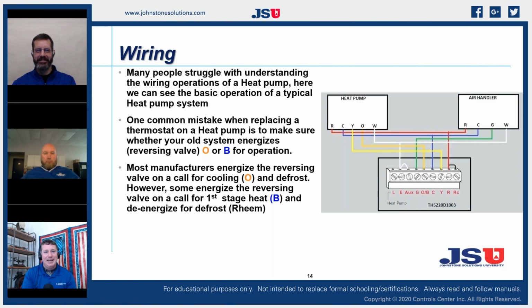So I would say that 80% or more of our industry uses O. What O is doing is energizing our solenoid, our reversing valve, for cooling. So the natural state of most heat pumps is actually heating. And then we energize O for cooling. There are manufacturers out there, particularly Rheem-Ruud, that have stayed with the B philosophy, and as far as I'm aware, are still using it. And I don't know of anyone else that's using that.